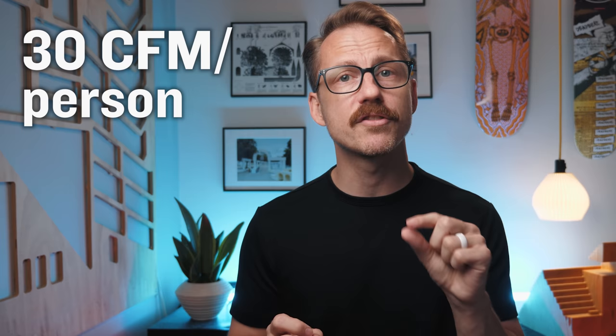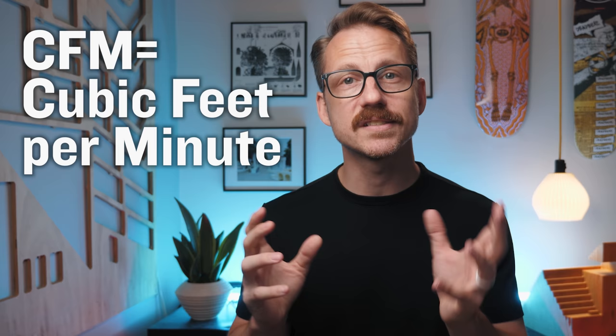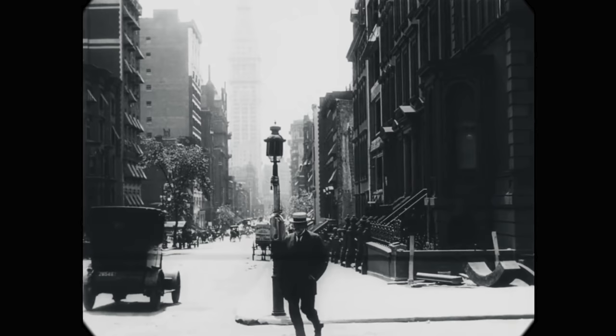By the 1880s, the amount of airflow suggested inside buildings was given a quantitative value, and the general consensus was that proper ventilation required 30 CFM — cubic feet per minute — per person. This is how many cubes with one-foot sides of air volume need to be replaced within a room in 60 seconds. In the US, 22 states had this value prescribed by law in 1925. This is actually a pretty high amount of airflow; it can make some people uncomfortable by being overly drafty. The typical rate today is quite a bit lower, as low as 10 CFM in spaces with minimal activity.